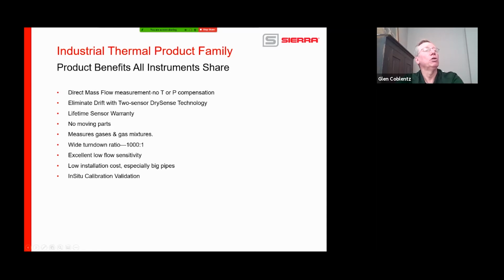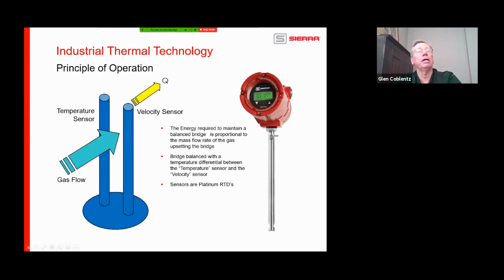Very, very low flow. Low installation costs, especially in big pipes. You can go with the insertion and you can do the in situ calibration validation. We'll talk more about that a little bit later. We mentioned this earlier. All of our legacy products have that 2-sensor design, 2 RTDs in there, Wheatstone bridge. So what you sacrifice with this is accuracy and field flexibility. But we still have, I was going to say tens of thousands, but we have over 100,000 of these in the field.